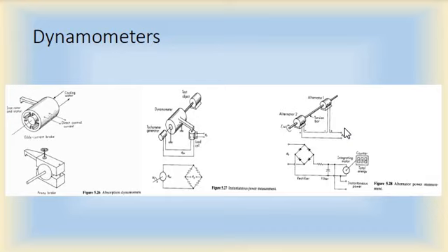When the shaft carries torque, that is, when the shaft is loaded, the shaft may twist or turn, which will cause a phase shift between the output voltages of these two generators. So as I said at first, when the shaft is unloaded, the output voltages will have no phase shift, and when the shaft is loaded, the output voltages will have a phase shift from each other.